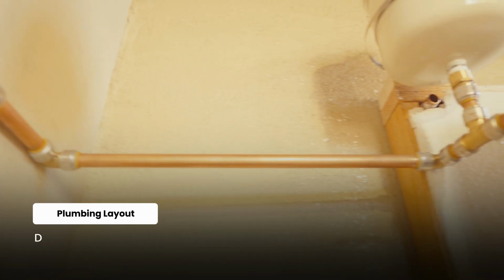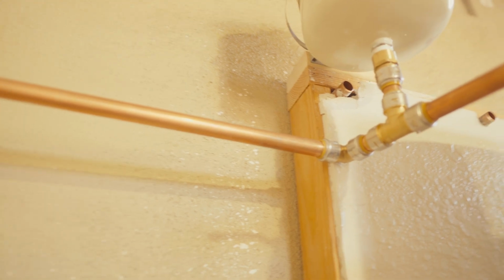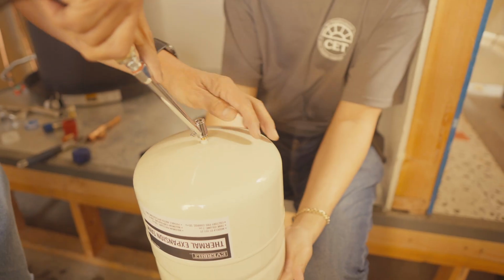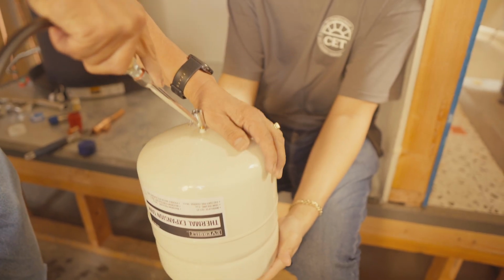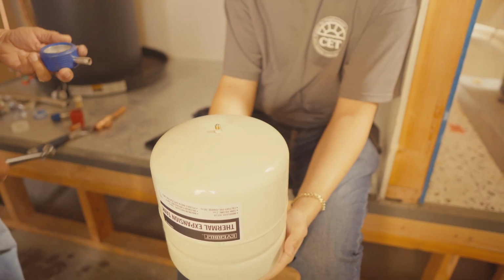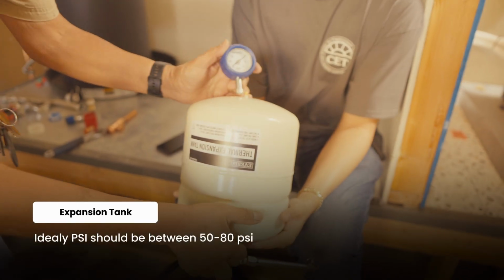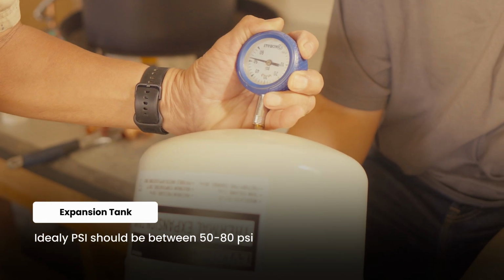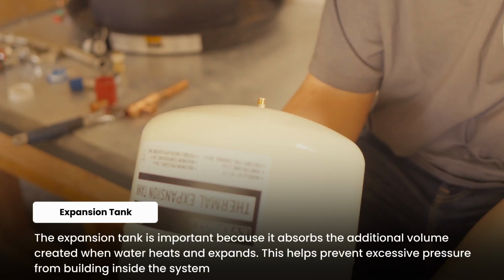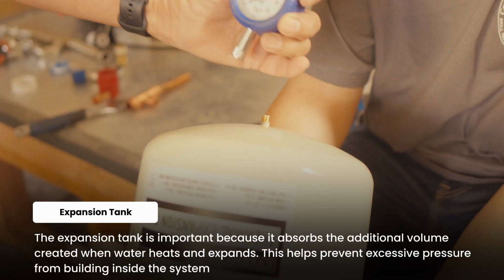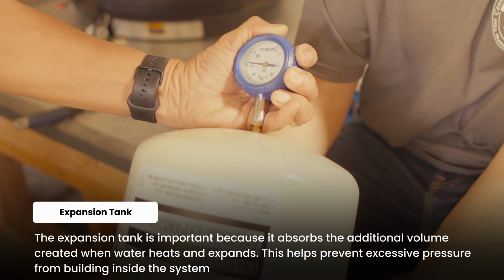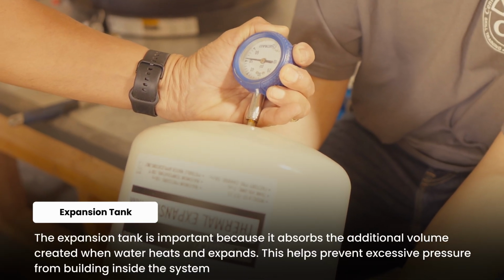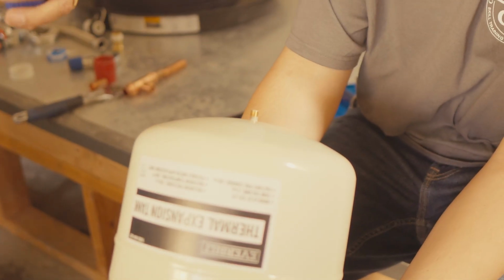In our setup, we begin by running a cold water line from the source to the expansion tank. If you haven't done so already, set the expansion tank to match static water pressure, ideally 50 to 80 psi. The expansion tank is important because it absorbs the additional volume created when water heats and expands. This helps prevent excessive pressure from building inside the system.